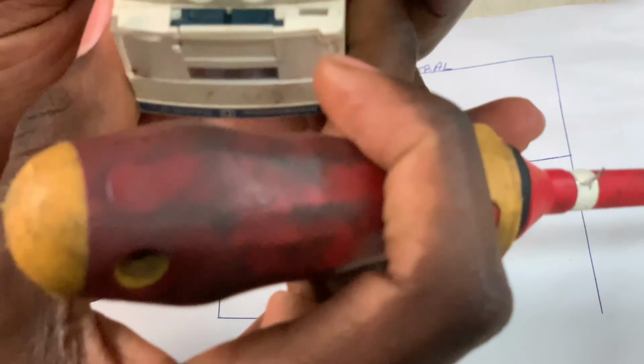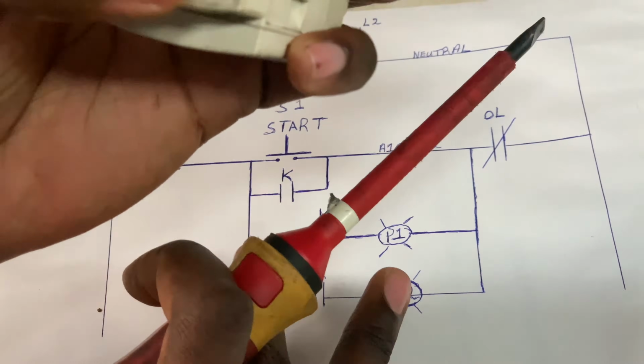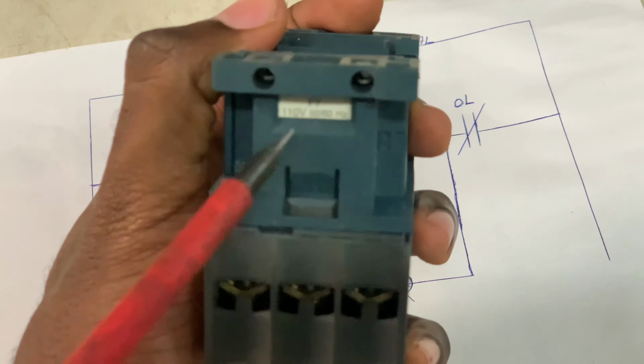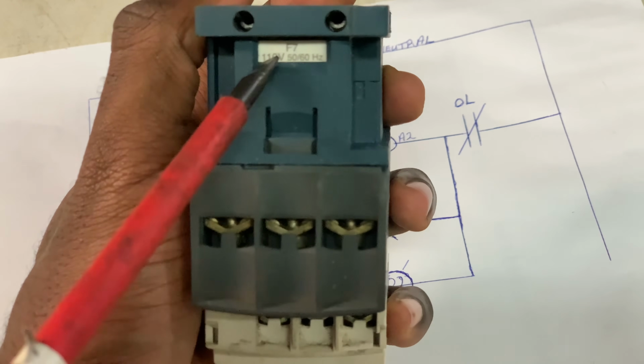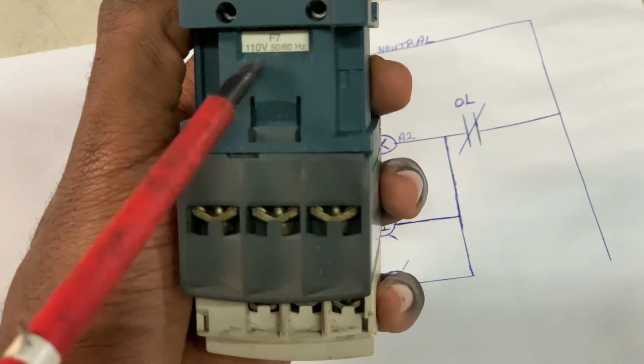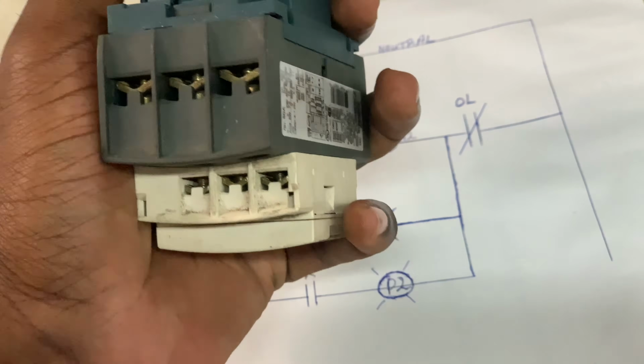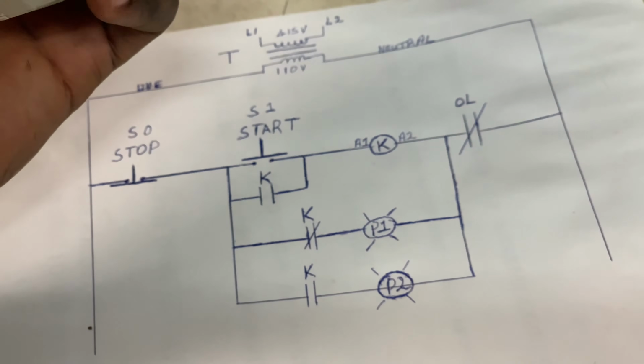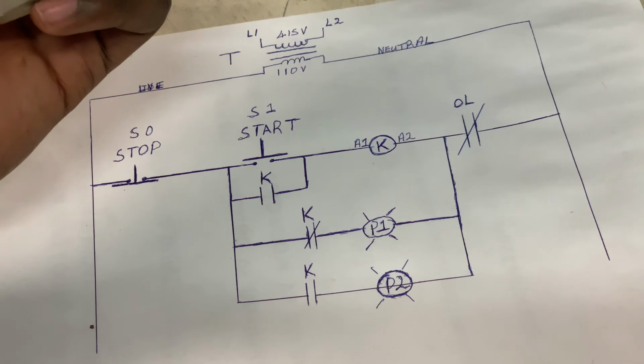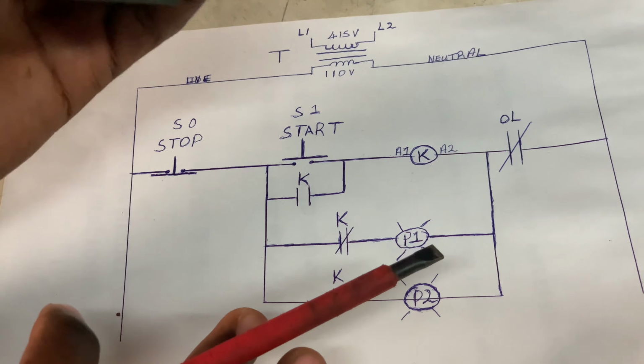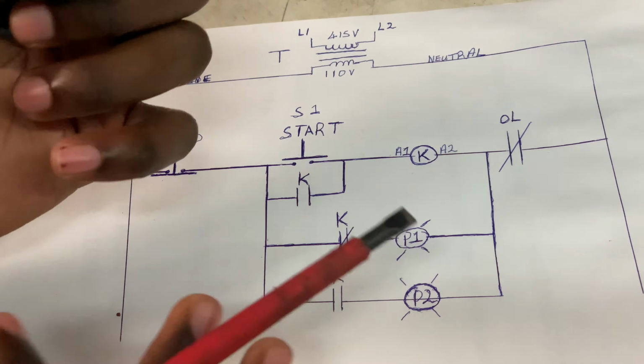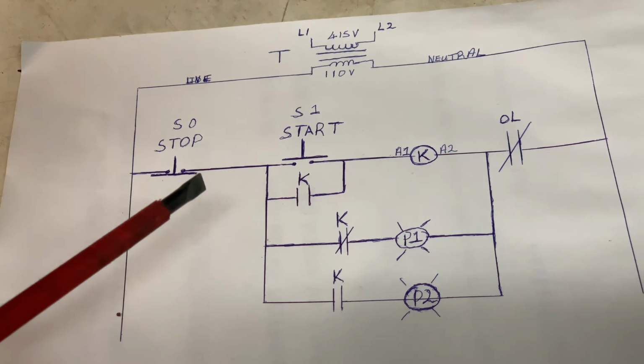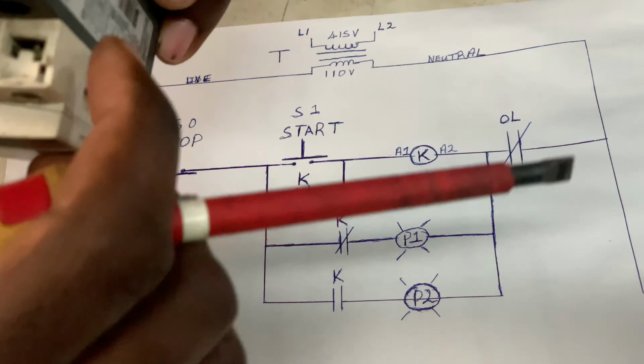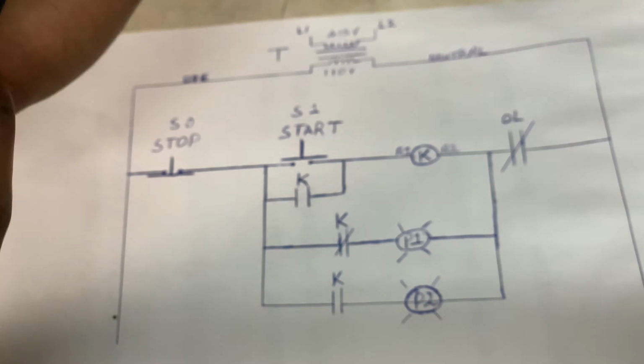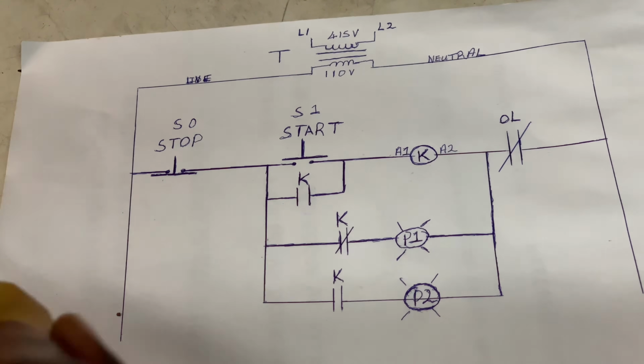So here you can see this 110 volts. So this contactor uses 110 volts. You have other contactors which use 24 volt DC, 220 volt, or some are even dual voltage, can use more than one type of voltage to energize the coil of the contactor. Alright, so you have to pay attention when choosing your contactor for your motor circuit.